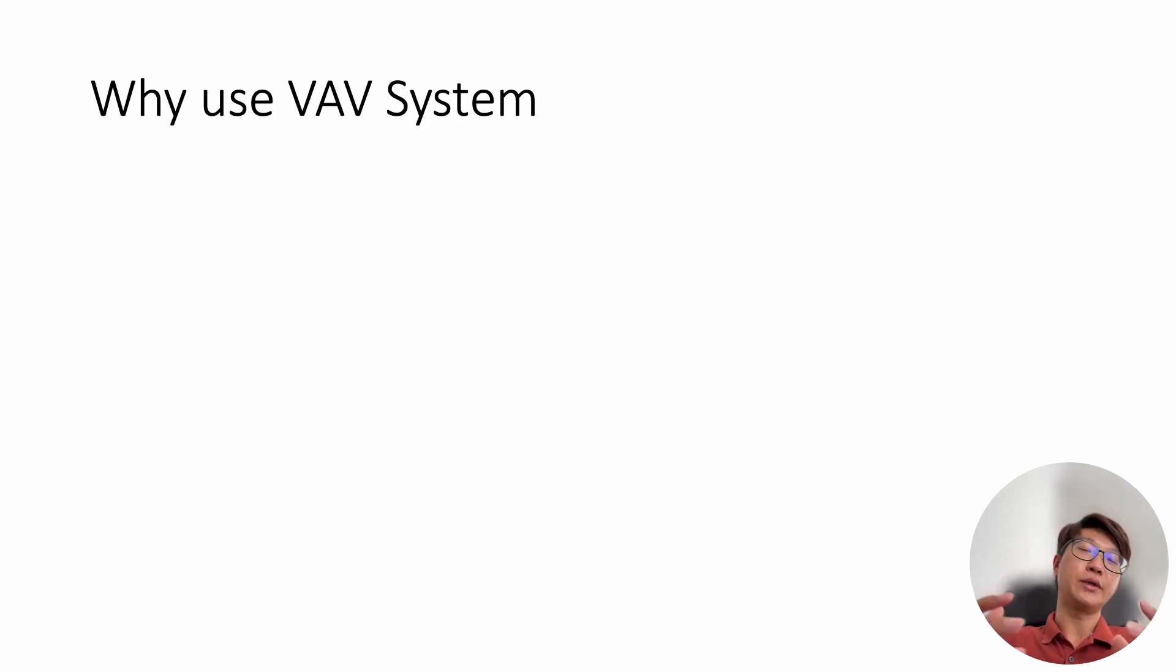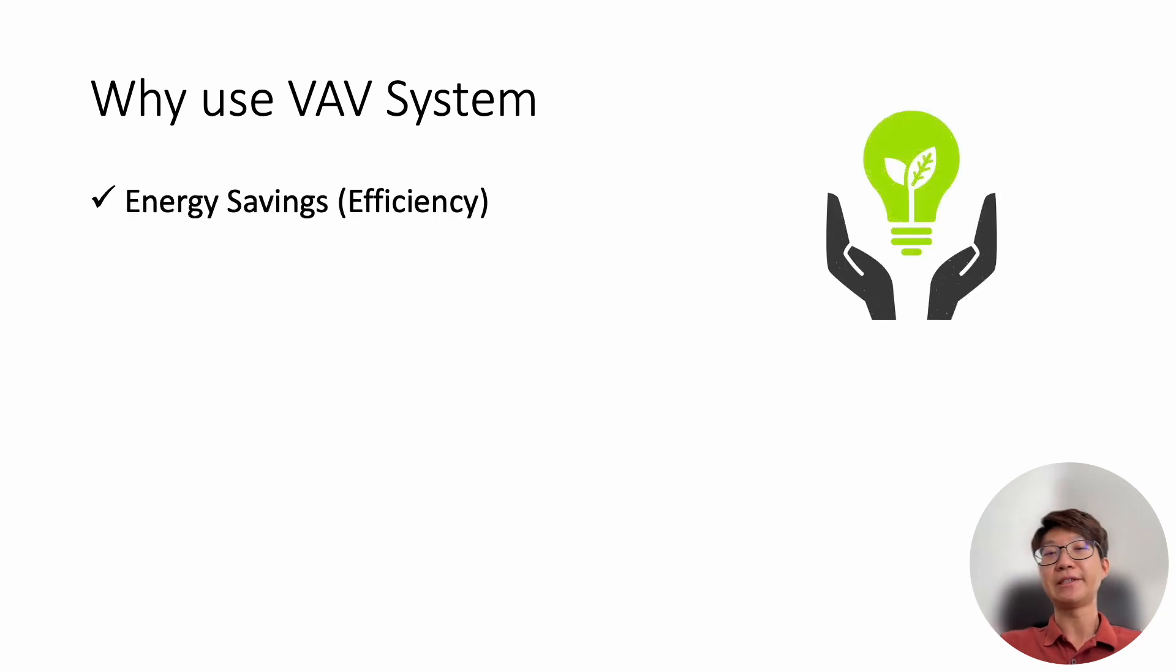So now why we want to use a VAV system? Why we want to vary the airflow? So the first thing obviously is the energy efficiency, the savings. Because traditional system, we have fixed speed. Here and there, sure, we have a few rooms that are too cold. But if you are using a traditional fixed speed system, you can't do anything. You can't reduce airflow, anything. So you just leave it too cold. Actually, you are wasting energy. So via variable air volume system, you can actually reduce the AHU fan speed. Then you save energy.